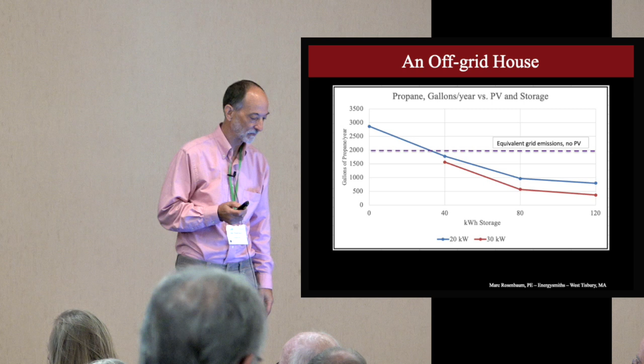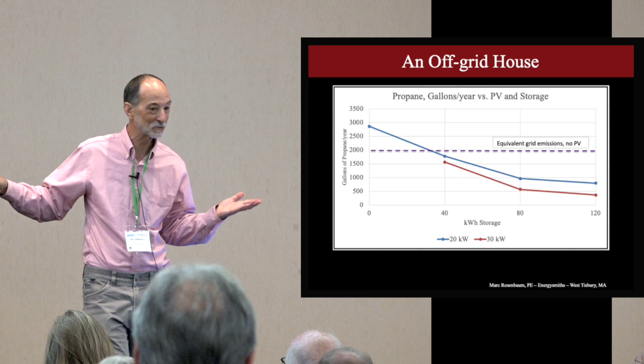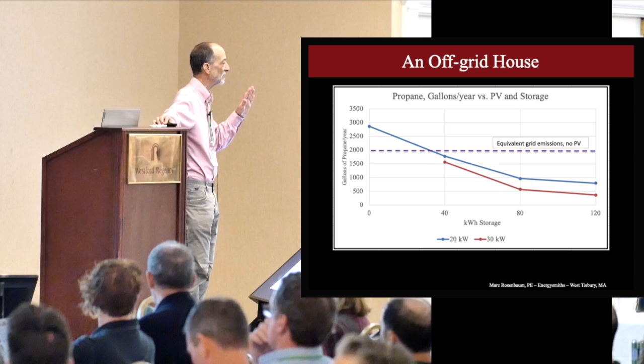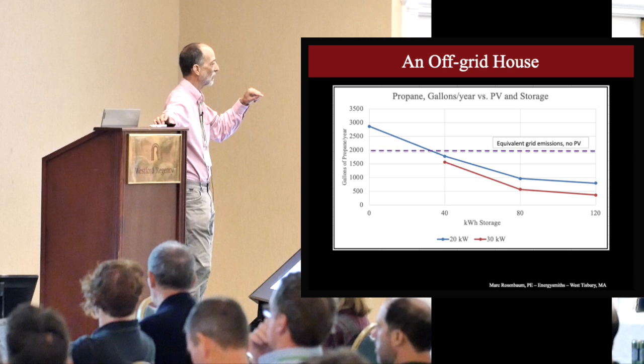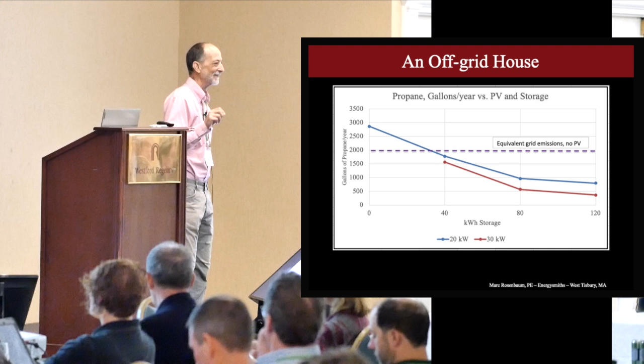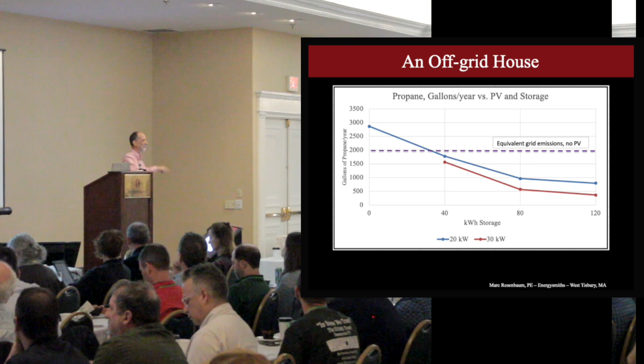So where we ended up is close to the end of that lower red line, and we're using about 300 or 400 gallons of propane a year. In the first weeks the house was occupied, we were on it closely, checking whether our model was validated, and it was within less than 10% off. Then it started to go up again — the freaking pool contractor had these wonderful inverter-driven variable speed pumps that we'd turn down to what we really needed, and every time the pool sub showed up, he turned it up to maximum. We could just see it in the data. Take off the knob, take off the knob. All right.